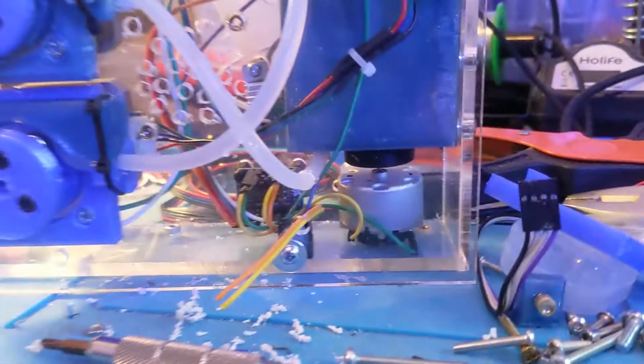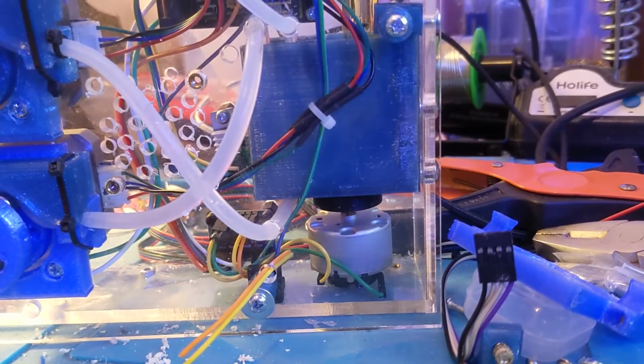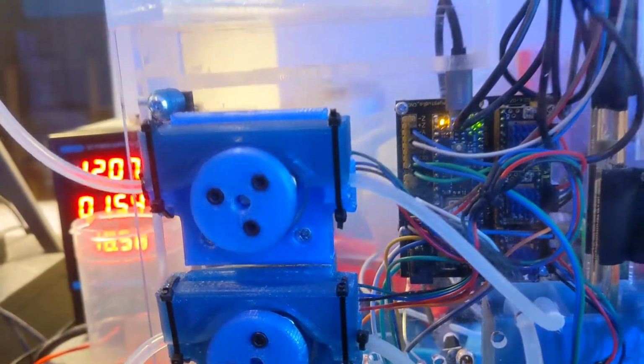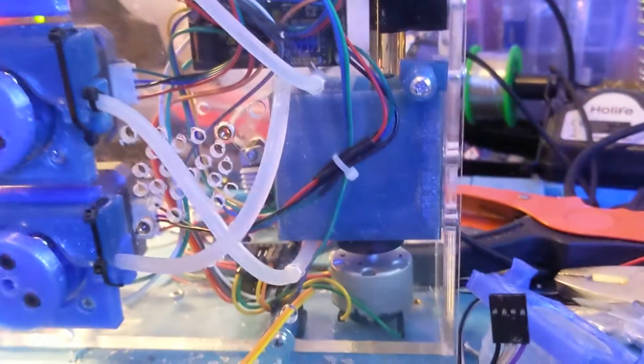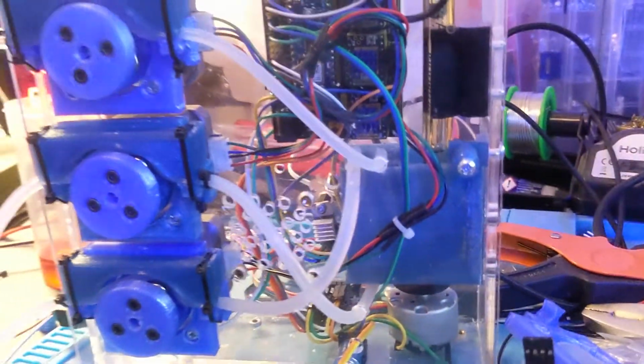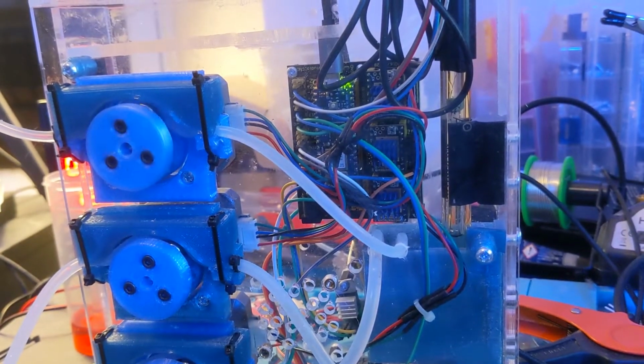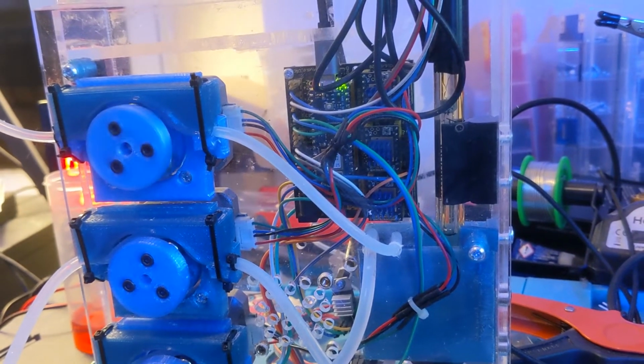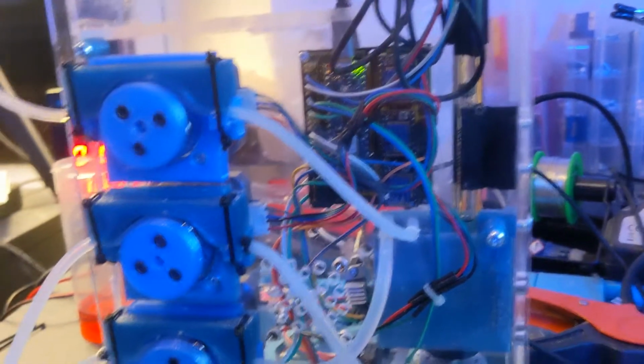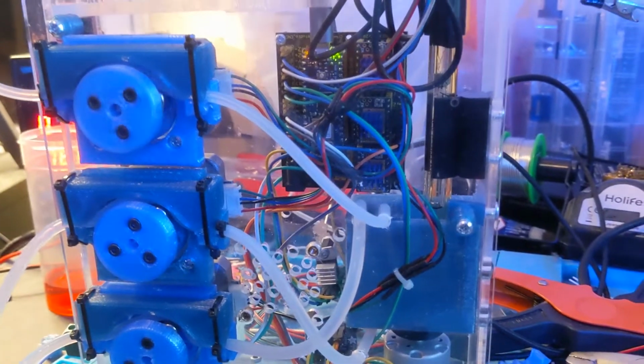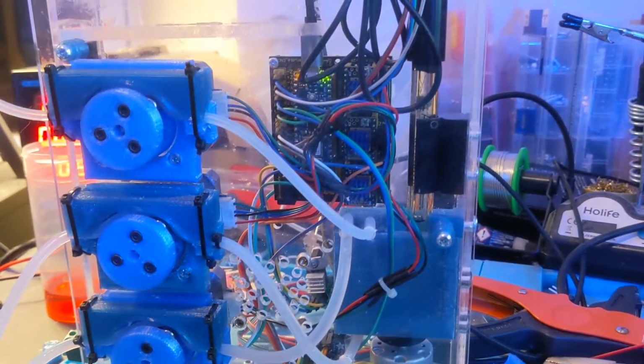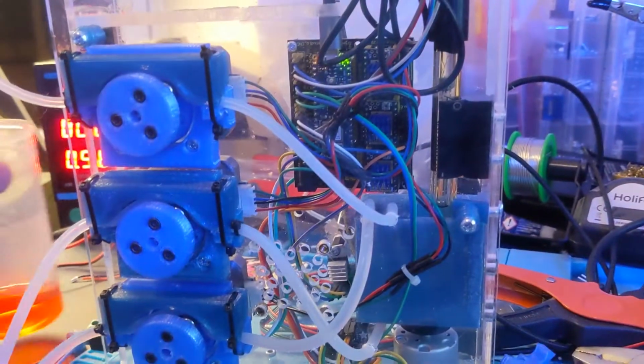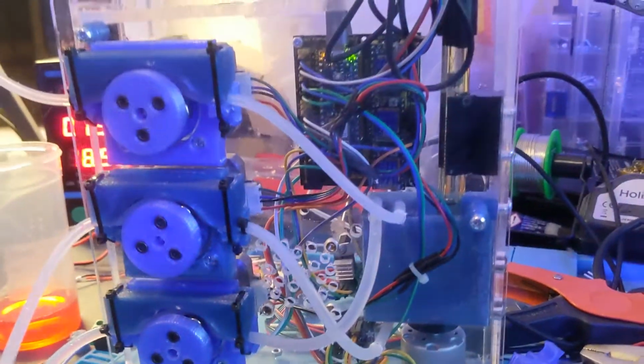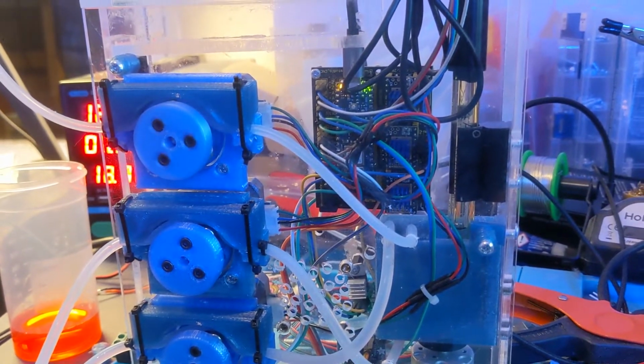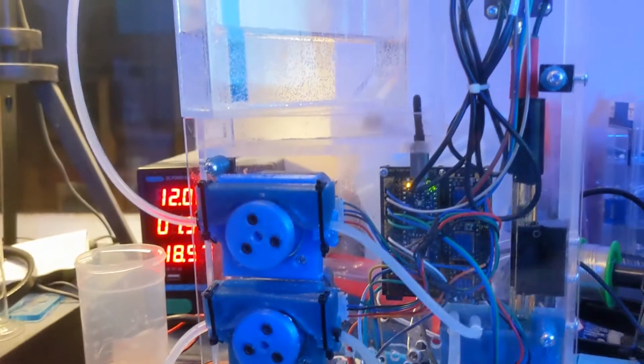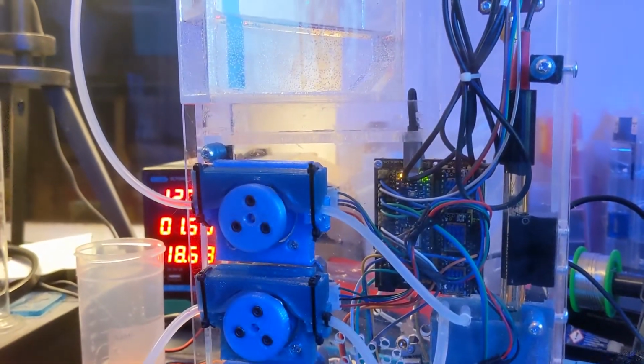You'll notice that that stirrer is running every time more of the reagent's titrated in, but then it stops for the pH measurement to be taken. And that's important too. The pH reading will be affected if the water is moving, especially since when I calibrated the pH probe using these standard solutions, I was not stirring them at the time, so that actually does impact your calibration. I'm going to put my phone down again, and I'll pick it back up when we've reached that 4.2.